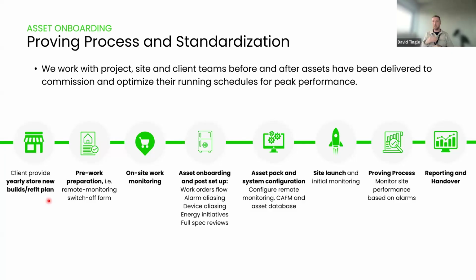We do that process to onboard all those assets. As part of that, we also pick up asset packs or asset data coming from those systems, plus F-gas and other gas details, to populate databases for any required regulations. End to end, our solution sits in between, but that also feeds into CAFM. So you end up with your control solution connecting to the asset and sending data out. It comes into this centralized solution covering alarm aliasing and device aliasing, making sure it's all aligned. The final piece links that to other solutions, be it a work order system or anything else.